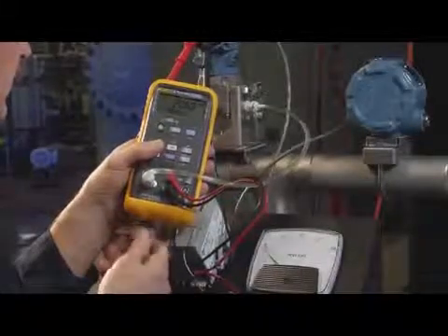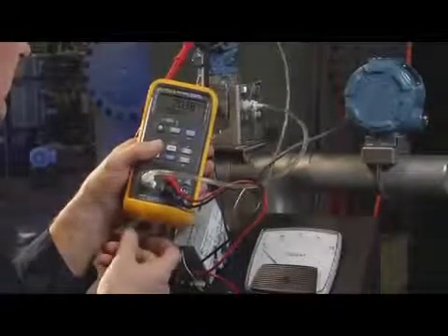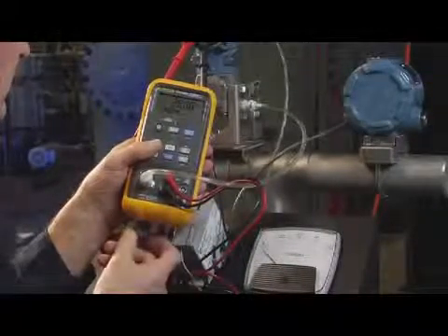Use the electric pump to generate 200 inches of pressure. Use the fine adjust in the pump to dial in the value to exactly 200 inches and verify for 20 milliamps. With 200 inches of water applied, the deviation between measured milliamp value and 20 milliamps is the calibration error of the transmitter.